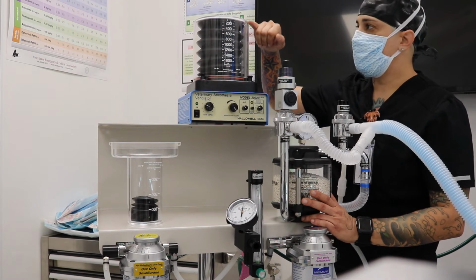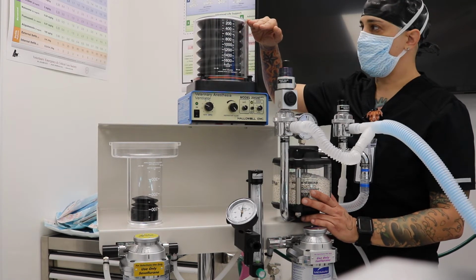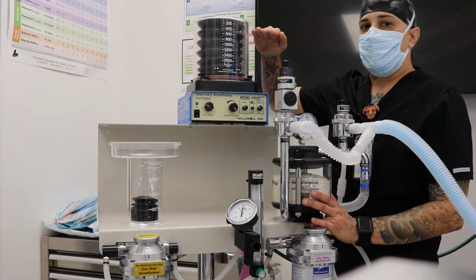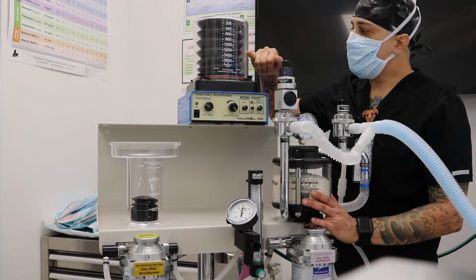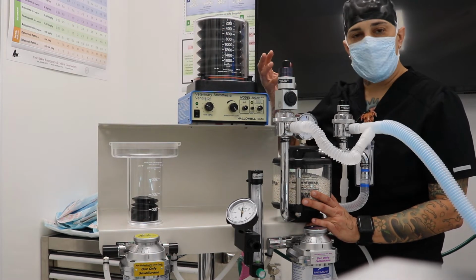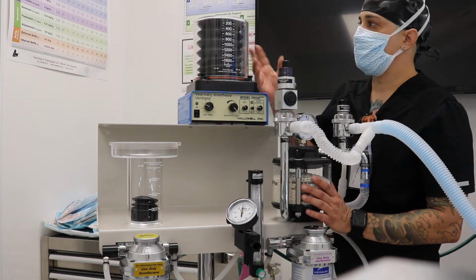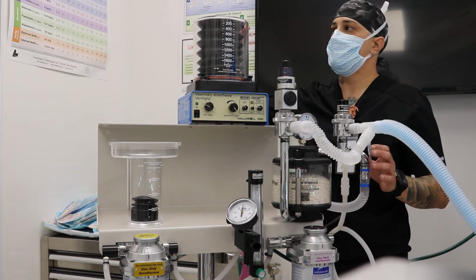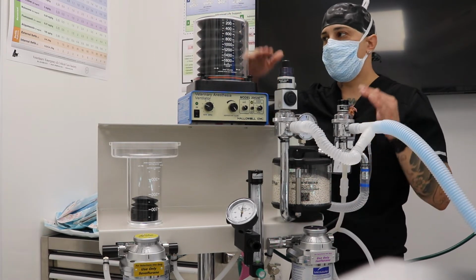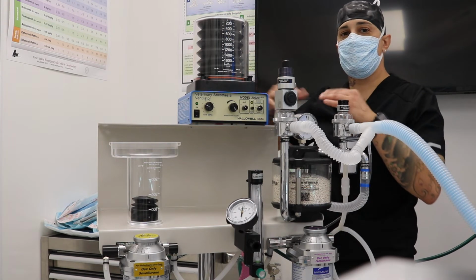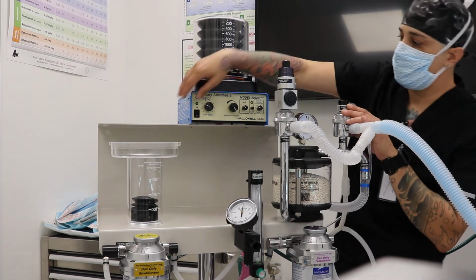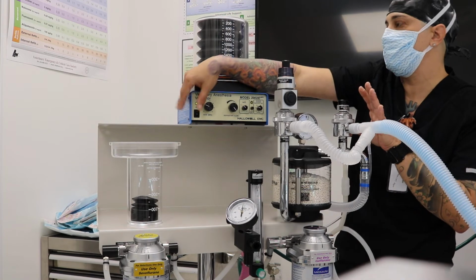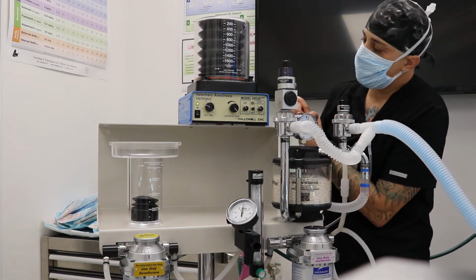Okay? The point of leak test is to make sure that the bellow goes all the way back up to the top. So if the bellow goes up to the top, when she gives a breath, and then gradually starts to decrease in volume, starts to go less and less, there's a leak somewhere and it needs to be investigated. So for this, I'm going to check it, let this bellow go up and down about 5 or 6 times, just to make sure that it maintains through the whole time. So go ahead and turn it on. We shouldn't hear any sounds. Let's see what we got.